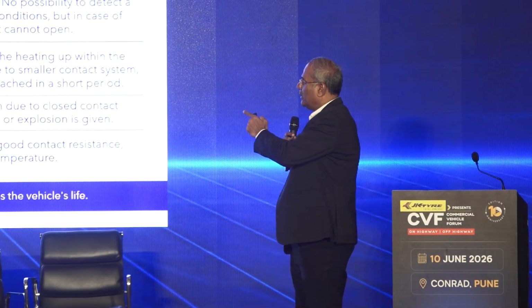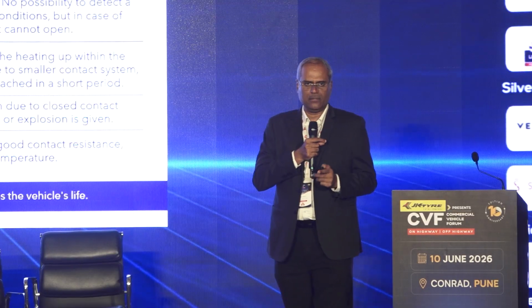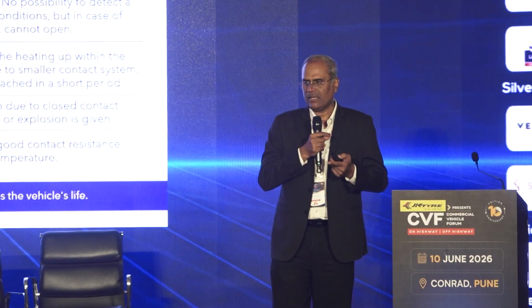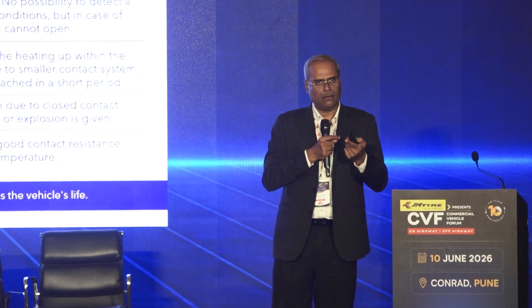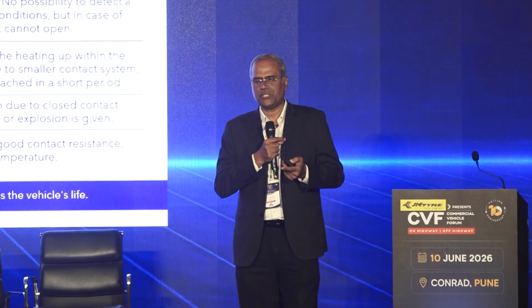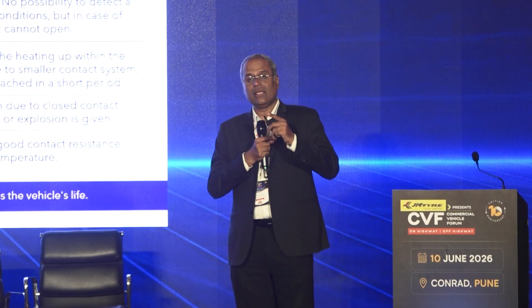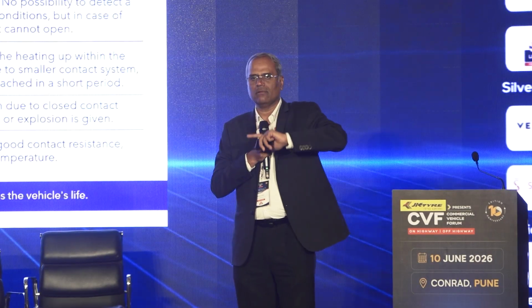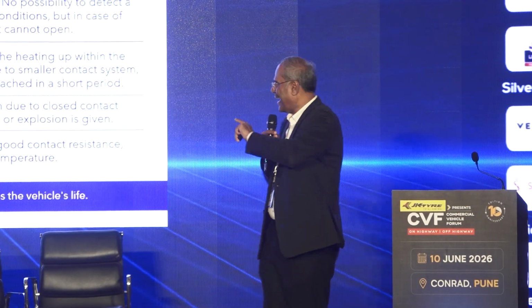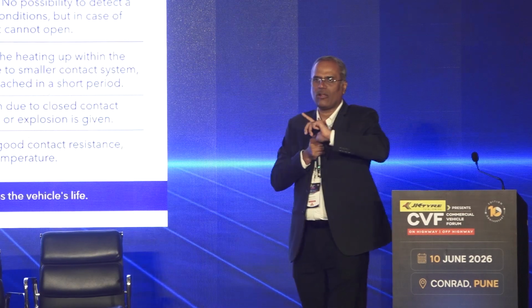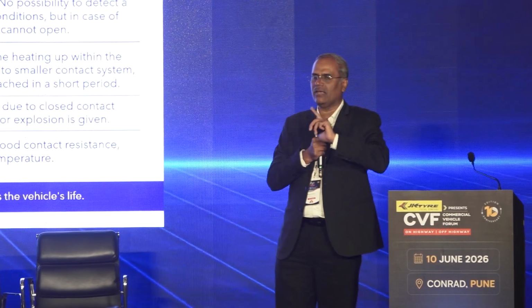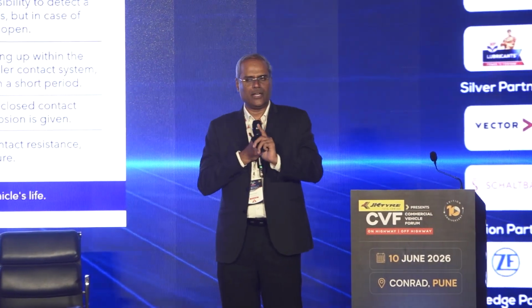So when we go for an open architecture, you get a safe, explosion-free ambience, because in normal conditions these will operate. But in an abnormal condition, say a fault, a gas encapsulated contactor cannot switch it - it mandatorily needs a zero current condition to switch.